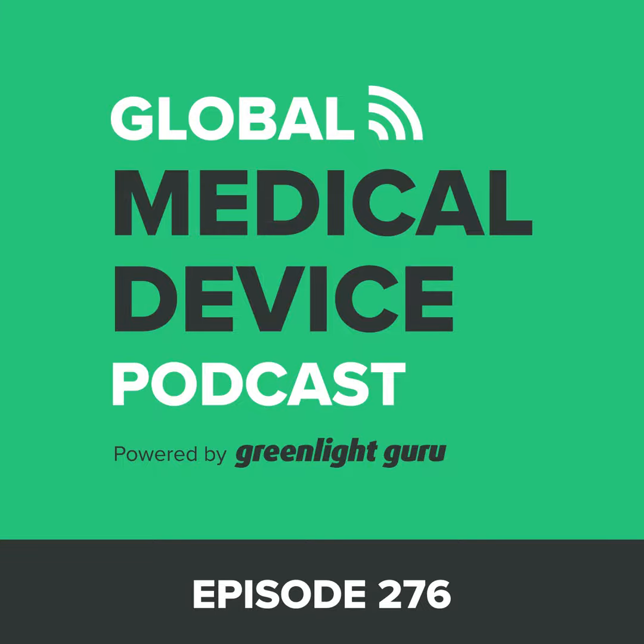And then the second module is this UDI and device registration. That's also voluntarily able to be used. It was open back in October of 2021. And I checked a couple of weeks ago, it has 96,000 records already in it. So people are making use of it. They're putting data in and you can walk down that. And again, that's voluntary at this point.